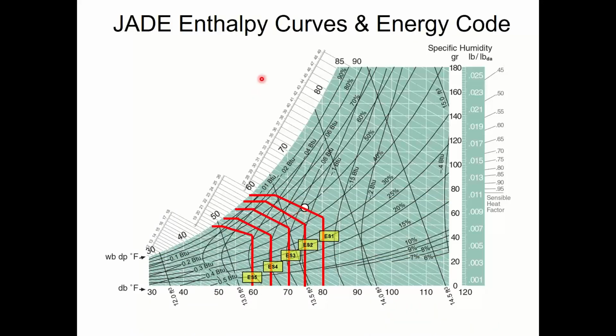Most of the economizer controls have enthalpy curves on them. This is showing a modern control, which is the JADE control, which is the code compliant control that almost every manufacturer uses. Some of them use a Belimo zip controller. Some of them use their own Johnson controller. But the vast majority of manufacturers use Honeywell, just the way it is. And these are the curves that are pre-built into that system.